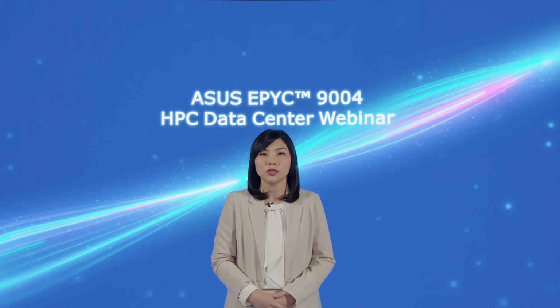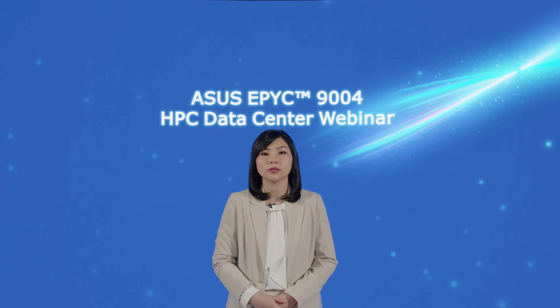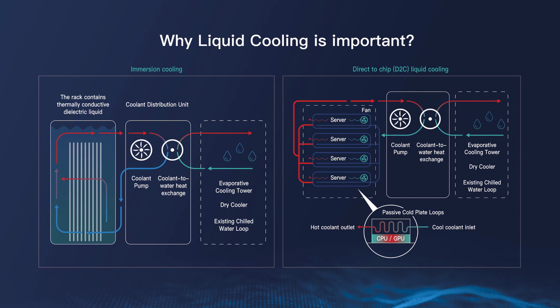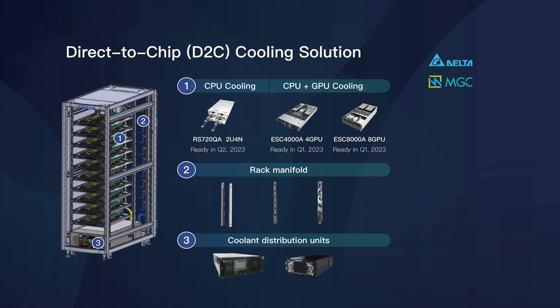ASUS introduced two types of liquid cooling solutions. One is direct-to-chip liquid cooling, placing a cold plate directly on top of components such as CPUs and GPUs, continually funneling heat through liquid coolant networks to a cooling distribution unit in the rack. The other is immersion cooling, which places an entire server in a thermally conductive dielectric fluid for maximum heat dissipation. The building blocks of direct-to-chip solutions at the rack level include rack manifolds, CDUs, and cold plates.